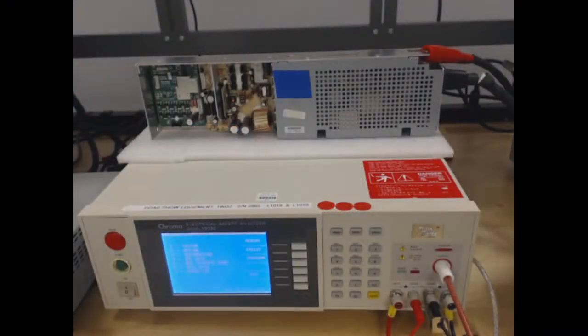Hey everyone, today I'm going to be showing you a ground bond test using the Chroma 19032 electrical safety analyzer. The purpose of doing a ground bond test, rather than the more traditional ground continuity test, is to ensure the integrity of your ground conduit.